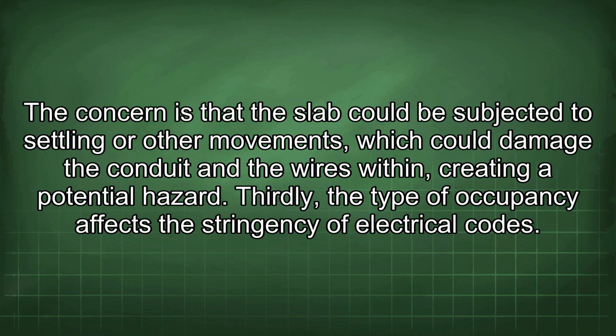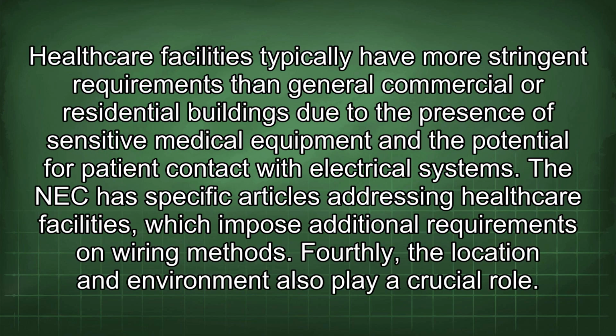The concern is that the slab could be subjected to settling or other movements, which could damage the conduit and the wires within, creating a potential hazard. Thirdly, the type of occupancy affects the stringency of electrical codes. Healthcare facilities typically have more stringent requirements than general commercial or residential buildings due to the presence of sensitive medical equipment and the potential for patient contact with electrical systems. The NEC has specific articles addressing healthcare facilities, which impose additional requirements on wiring methods.